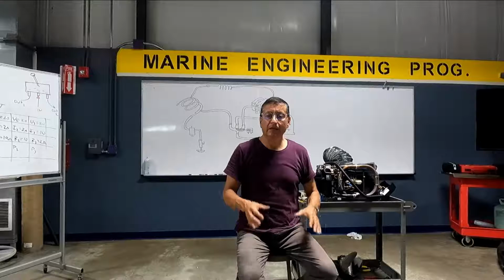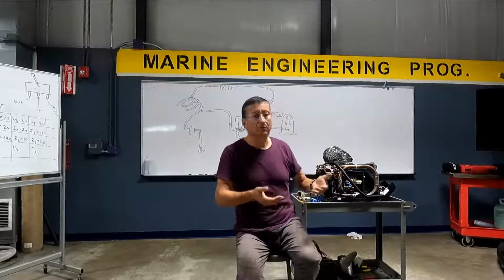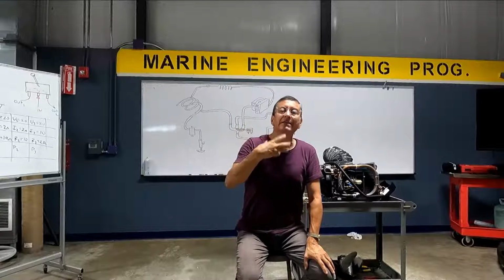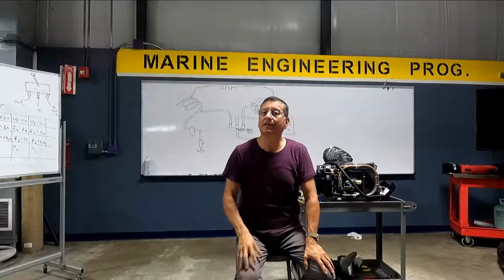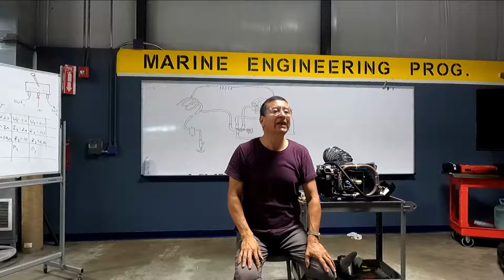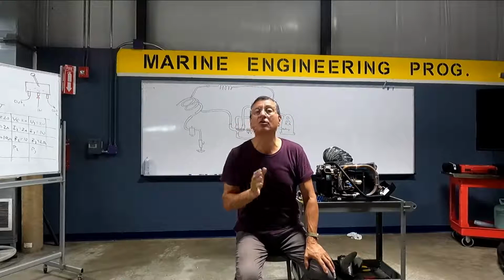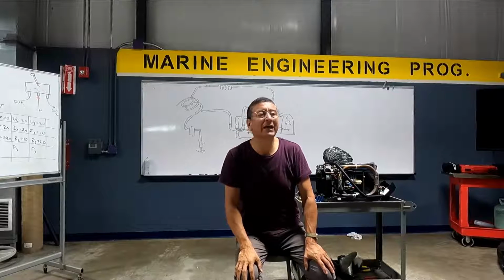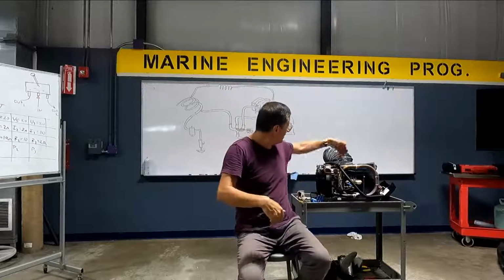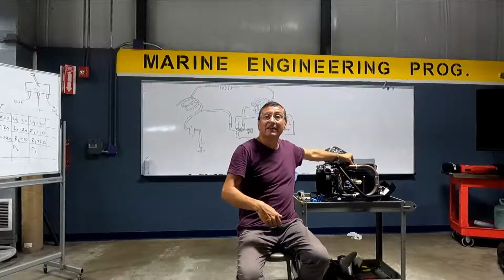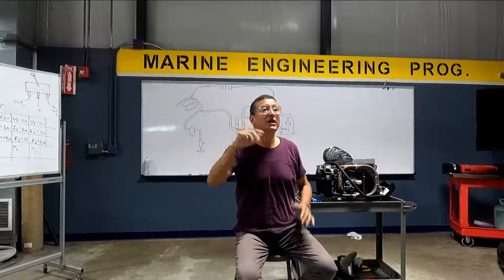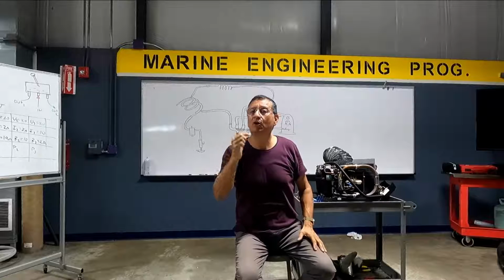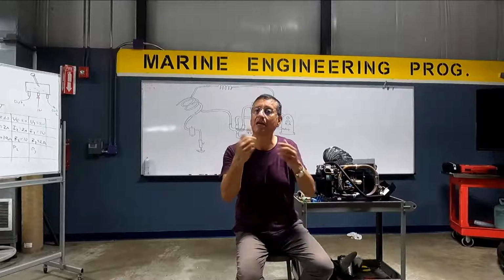Normally, in the typical air conditioning unit, like the air conditioner of your home, the coil that you have inside is the evaporator. And if you touch the pipes of that inside coil, those pipes are frozen. And if the air filter is clogged, what happens? No air circulates through those frozen coils, and ice is created and blocks that radiator, the indoor coil.